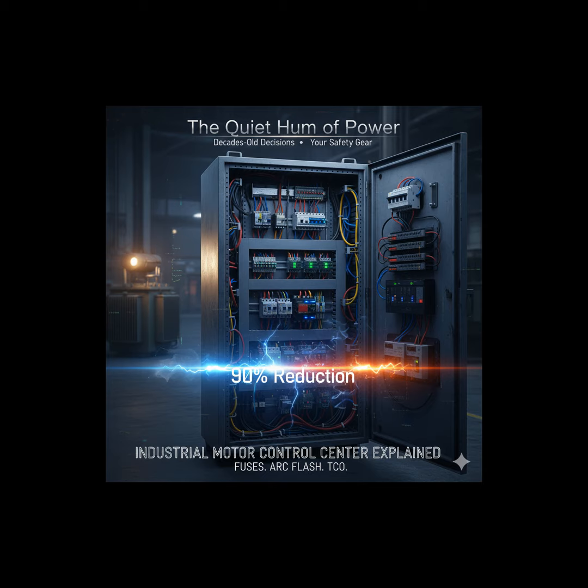And crucially, current-limiting fuses act incredibly fast. They can clear a fault in as little as 0.004 seconds. That's before the current even reaches its peak potential during the fault cycle. And breakers? Circuit breakers, conversely, are mechanical. They use sensors, thermal or magnetic, to detect the overcurrent, which then triggers a mechanical contact separation. While they are reliable and resettable, they require time for that mechanical movement, often clearing the fault significantly slower than a high-speed fuse.